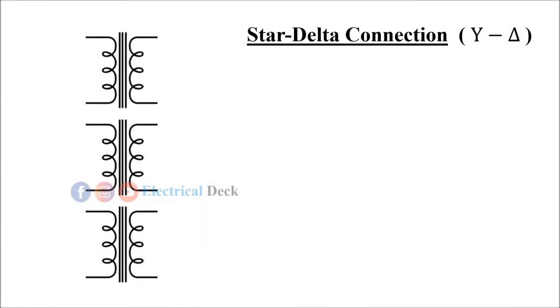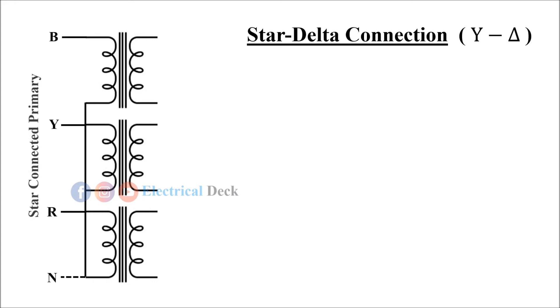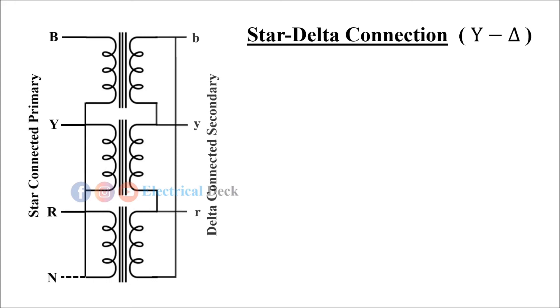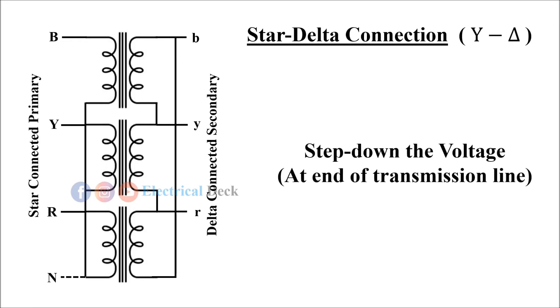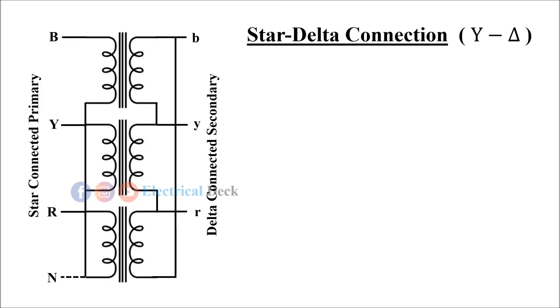In star-to-delta connection, the three-phase primary winding is connected in star while the secondary is in delta. This type of connection is commonly employed at the substation end of the transmission line. The main usage is to step down the voltage. The neutral available on the primary side is grounded, and there is a phase difference of 30 degrees between primary and secondary line voltages.